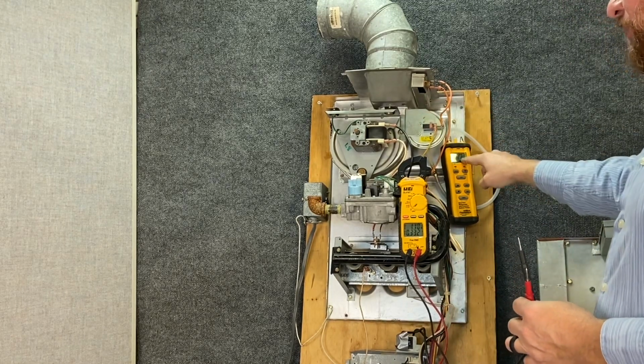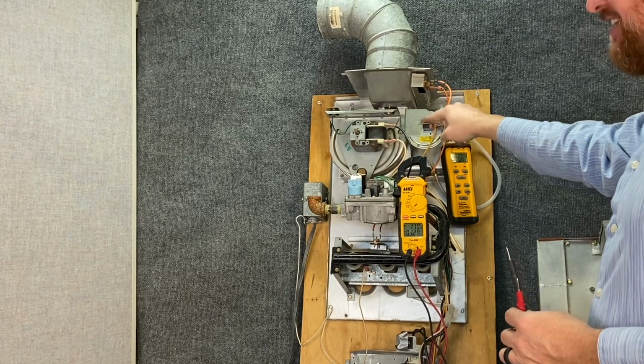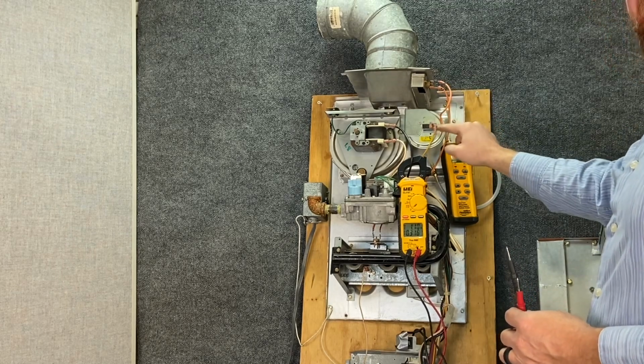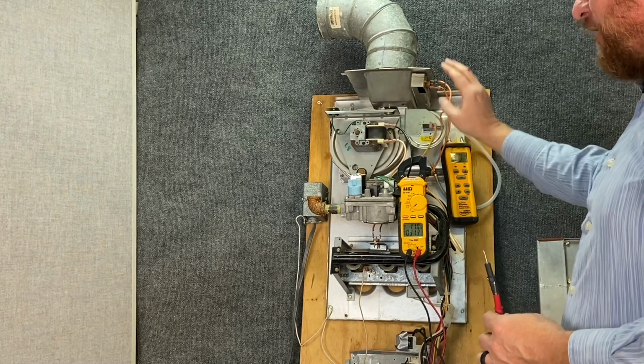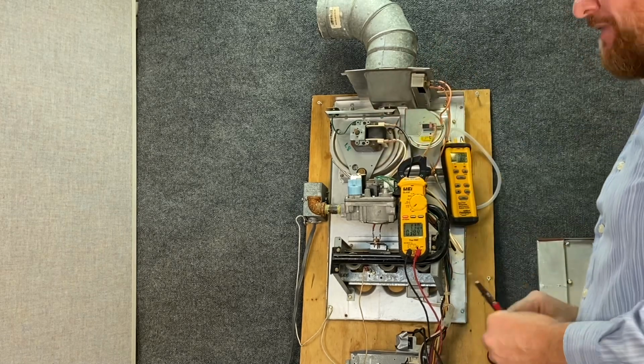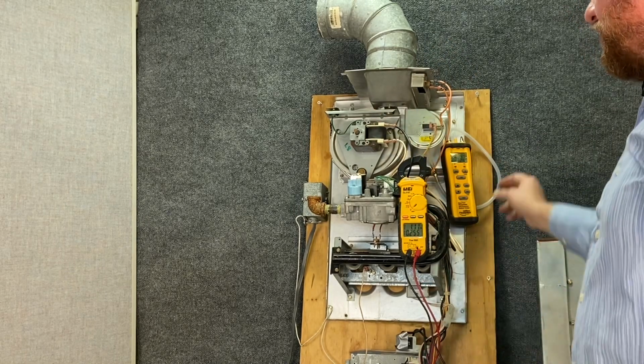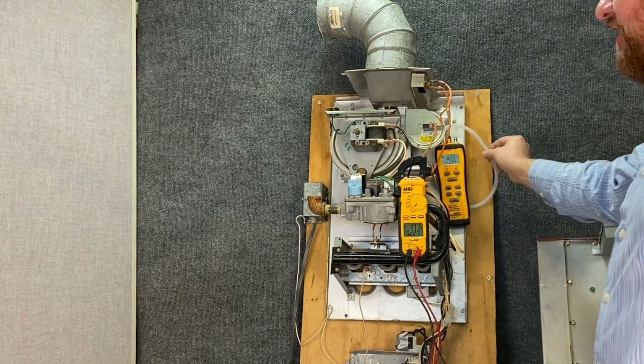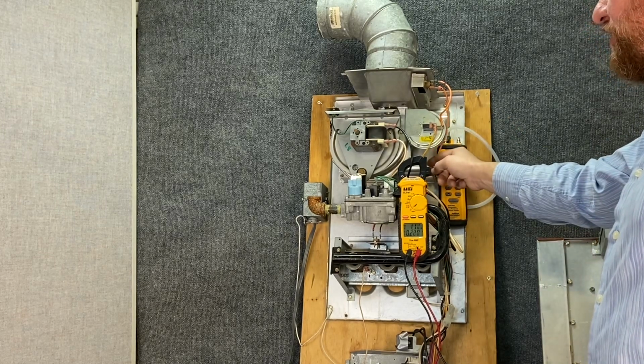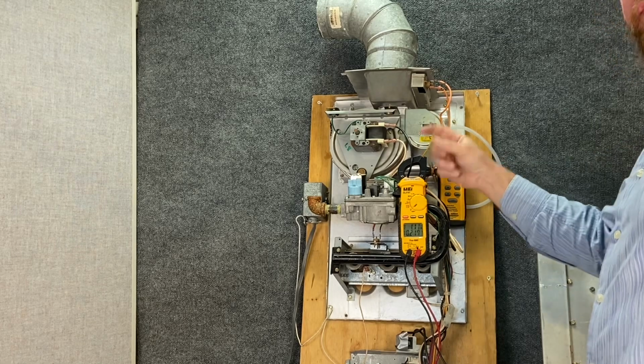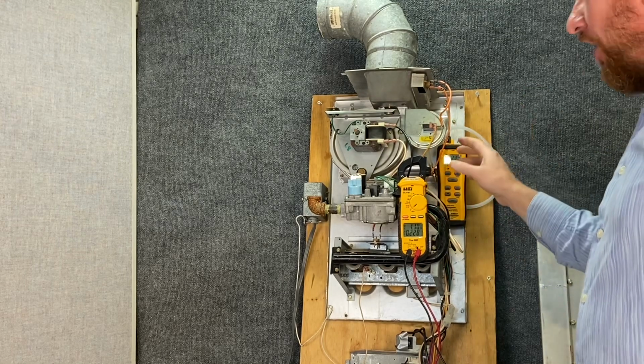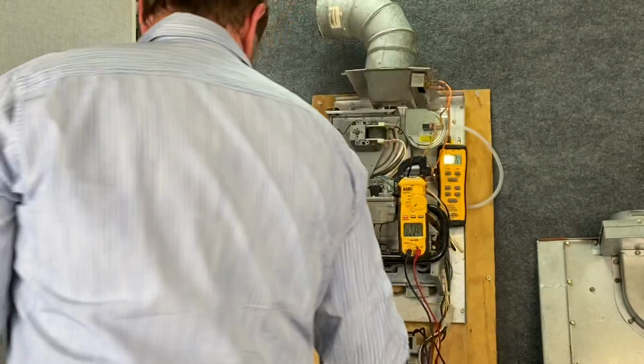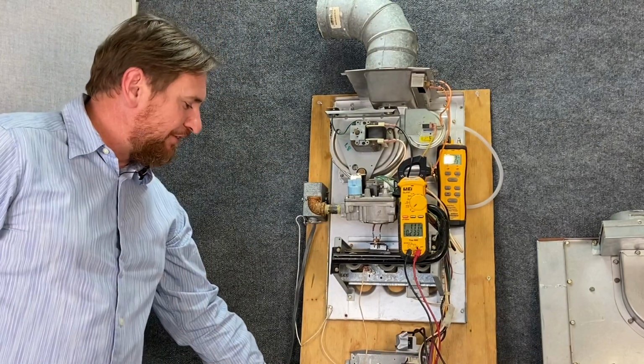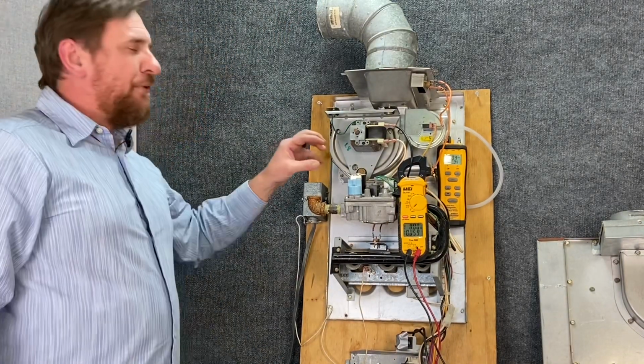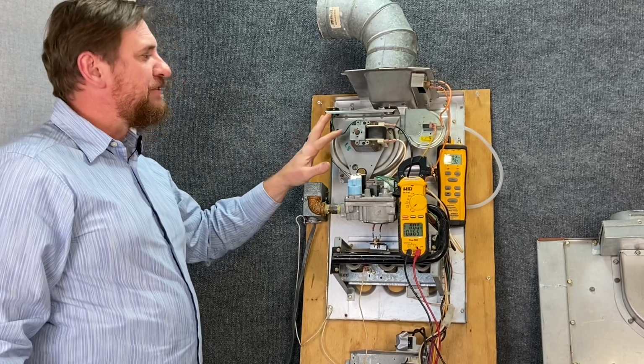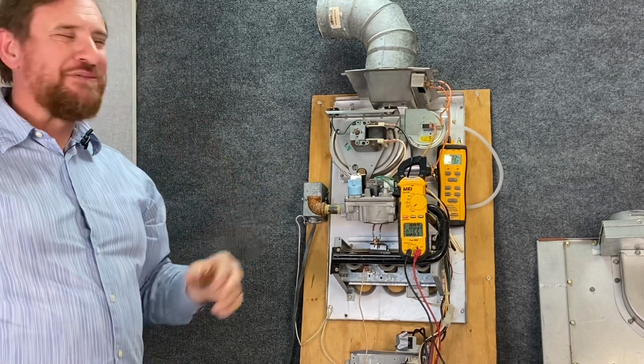I know I'm not pulling enough vacuum for the switch to close, and I've checked and my switch is open. So it's not a switch problem, I have a problem with my fan. Now before you can condemn that fan, you also want to check these little rubber hoses. They're notorious for getting dry rotted and cracked. So I would pull this hose off and inspect it. All of these steps are essential for working on these inducer draft motors. When I pull this motor off, it comes to a nice slow stop so we can actually hear what's happening.